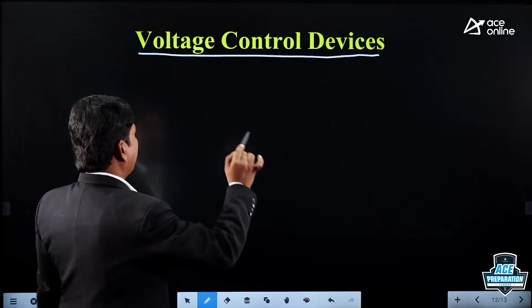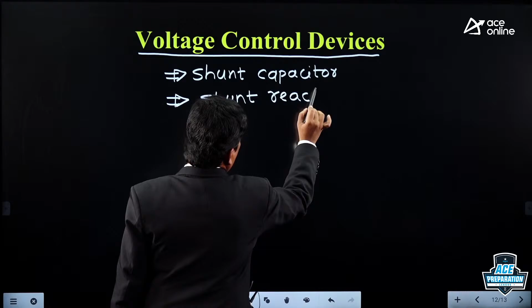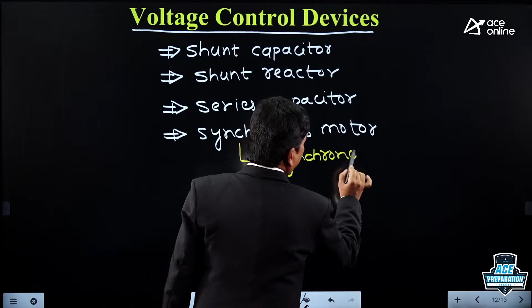So if you see the voltage control devices, shunt capacitor is one of the voltage control devices, and shunt reactor we are having, and series capacitor we are having, and synchronous motor. In case of the synchronous motor, we are having several constructions based on the excitation. So we will be having synchronous condenser or capacitor, and synchronous reactor, and also we will be having synchronous phase modifier. Clear? So these are the devices we are having to control.